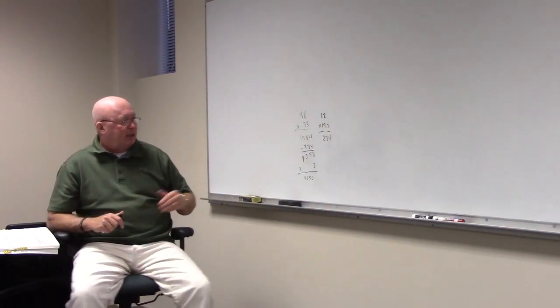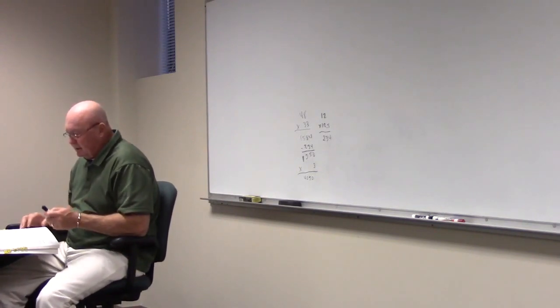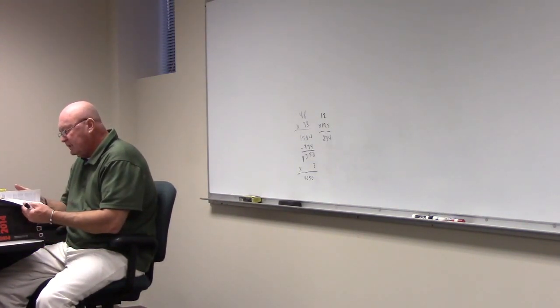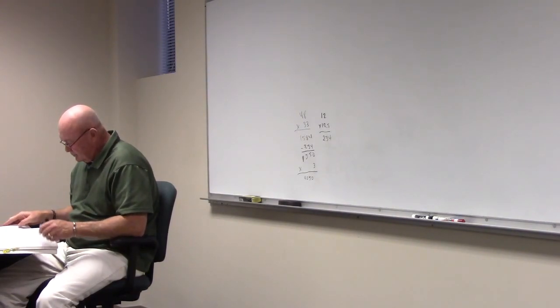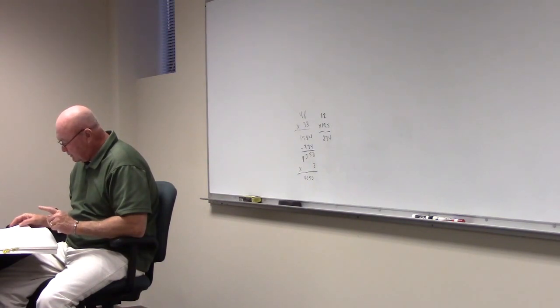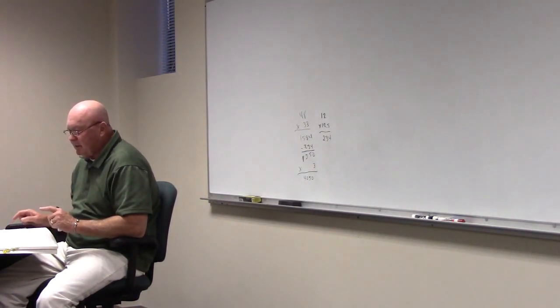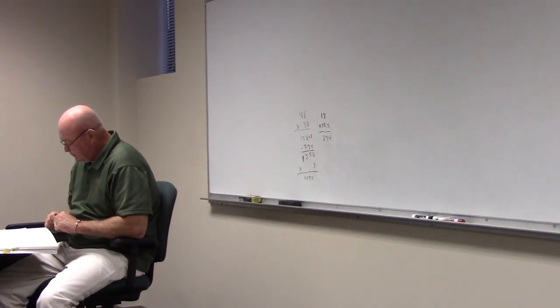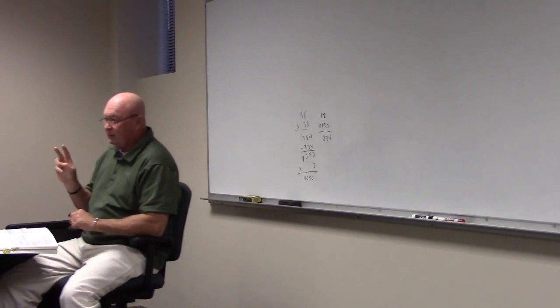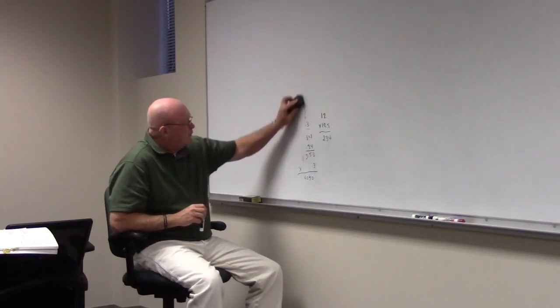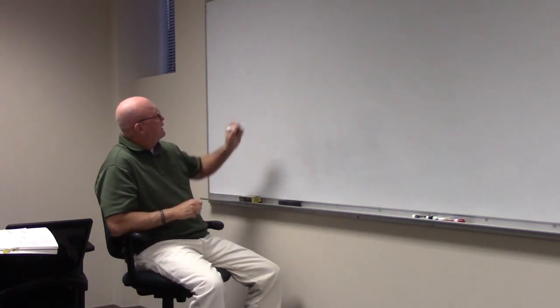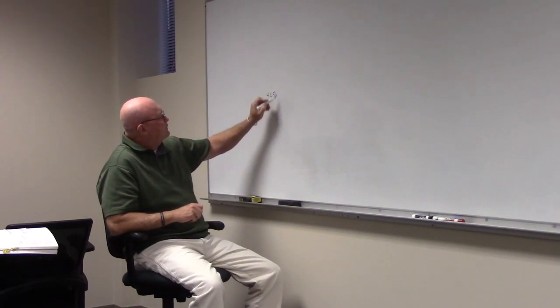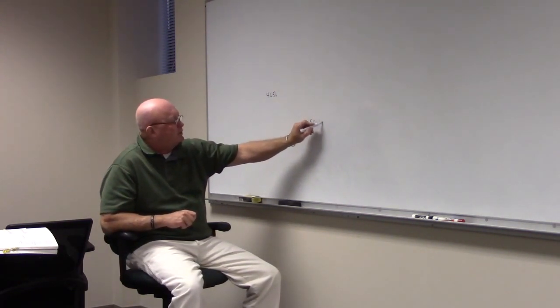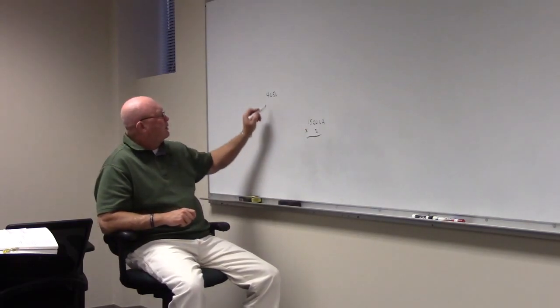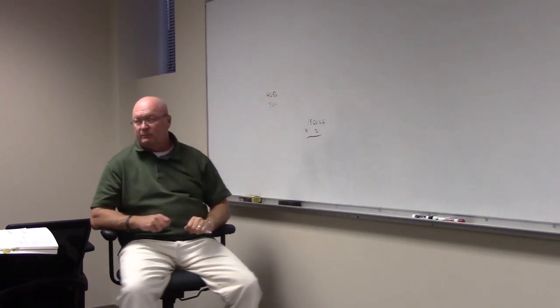The next step, if we turn to 210.11(C), it says in a dwelling, what does it say about small appliances? 210.11(C). What does it say about small appliances? You gotta have 2 or more 20 amp. Yeah, 2 or more 20 amp. So, well, first of all, I don't want to forget this 4,050. I'm going to write it down. So we got 2 small appliance circuits. Those are 1,500 volt amps each. So we're going to go 2, and so our small appliance load is going to be 3,000. Go with me on that?